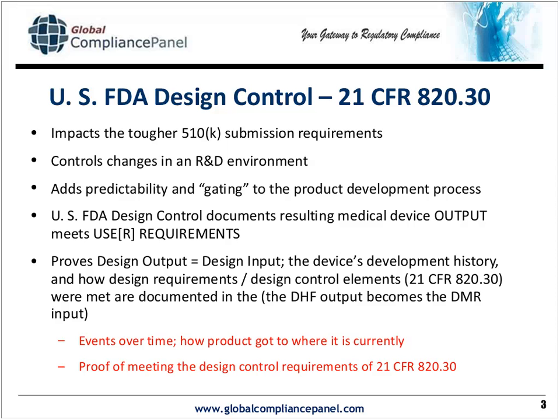And one of the things that will be a theme throughout this discussion is the fact that some companies choose to use design control throughout the entire life cycle of the product, from cradle to grave, so to speak. Others choose to use it just in the very beginning, the R&D to design transfer stage, and then they close it out to the device master record, et cetera, and change control under the overall company's GMP change control system. And we'll talk about that possibility a little later on as well.